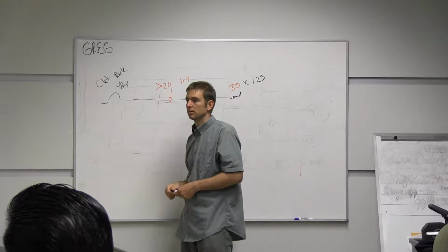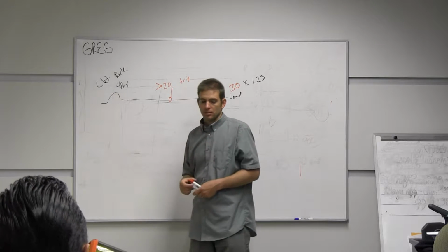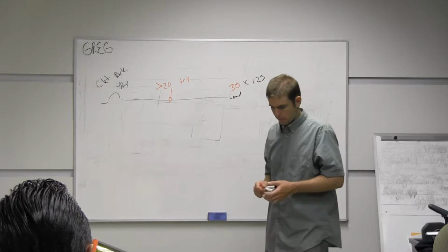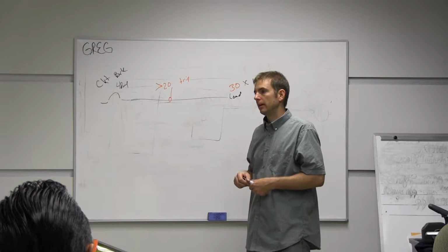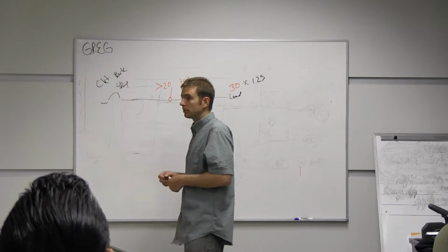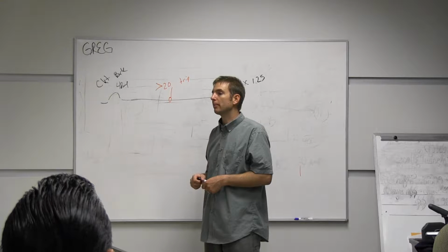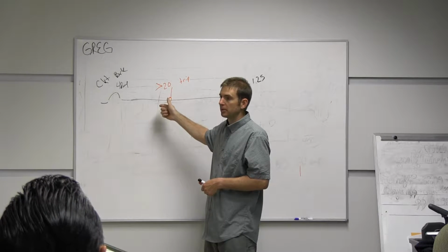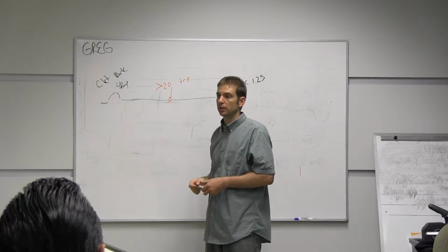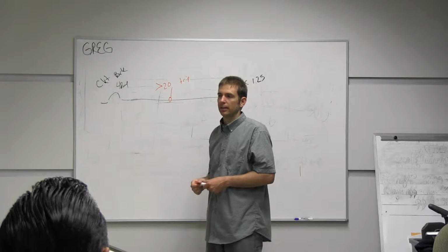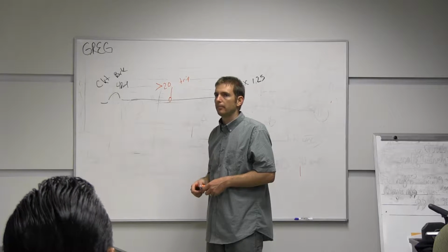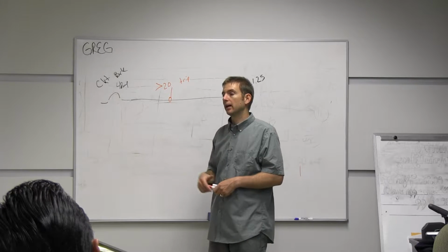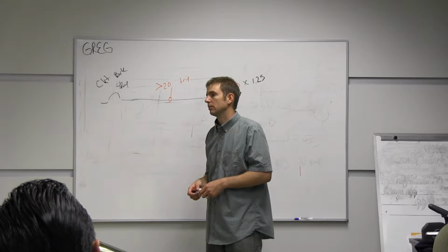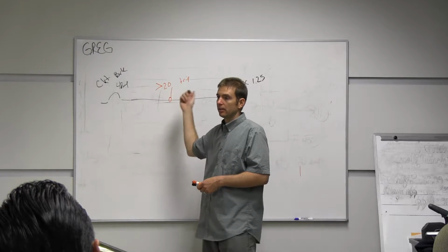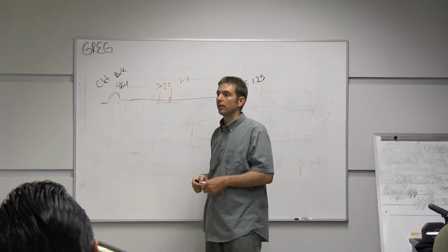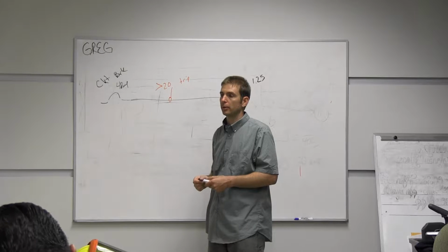If you want to test it, make sure that they do trip. I've never heard of anybody in a facility doing that. That's possible. If you have a load that you could place on a circuit and then you're clocking it with your amps to see that it trips when you exceed 30 amps on it, you could physically do that. I don't know if there's a need to do that though. I don't think there's any maintenance requirement in the industry or at Caltrans that would say that should be done. Make sure they actually function. There is, like I said, turning them off and turning them back on again. But as far as making sure that they trip, no, I've never heard of a requirement that does that.